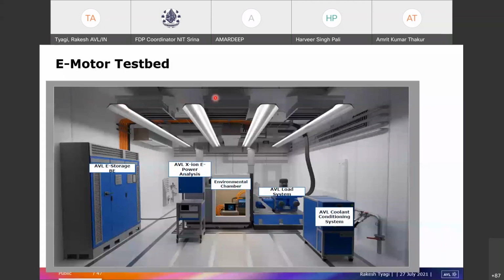Mainly we use the same temperature always, to see the performance. If you are doing different performance tests and your environmental conditions are not the same, you cannot correlate the data. Also if any accident happens, any leakage or problem with any equipment or UUT or systems, exhaust blowers are installed so they take care that fire, smoke, or anything goes out.